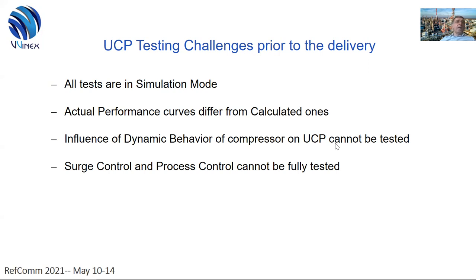That's why all tests and software simulation hardware verifications are done in simulation mode. You can simulate and connect as many input and downstream signals as you want to the UCP panel, but modeling the exact behavior of the compressor or blower requires more attention. Furthermore, the actual performance curves play a very important role. The real tested compressor has a different performance curve and even a different performance map than the initial calculated one. The dynamic behavior of the compressor is also different from the calculated one, and the surge control routine and process control routines of the UCP cannot be tested at simulation mode at vendor premises, as the compressor or blower are not physically there.